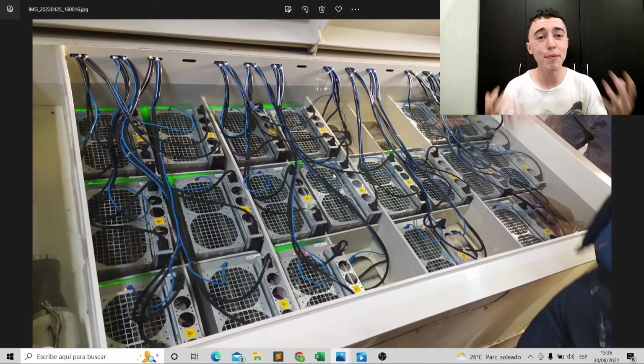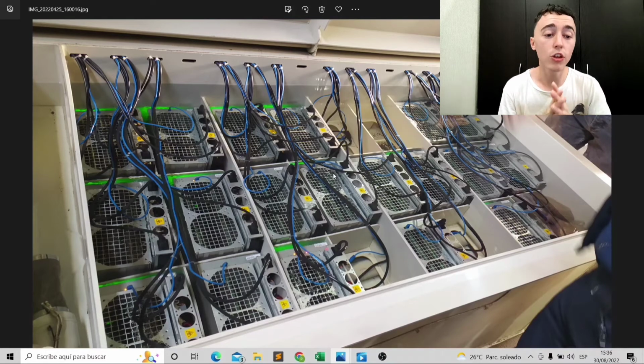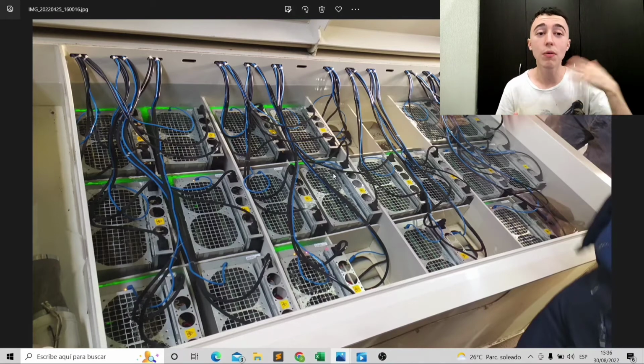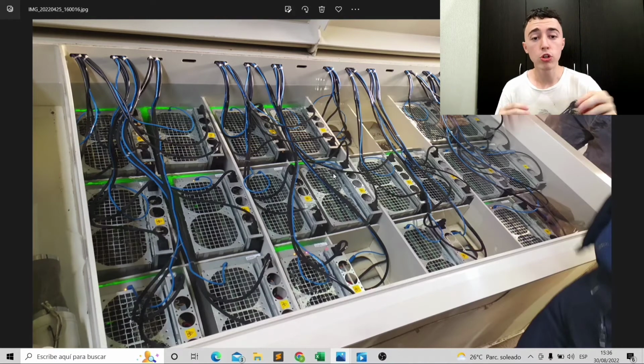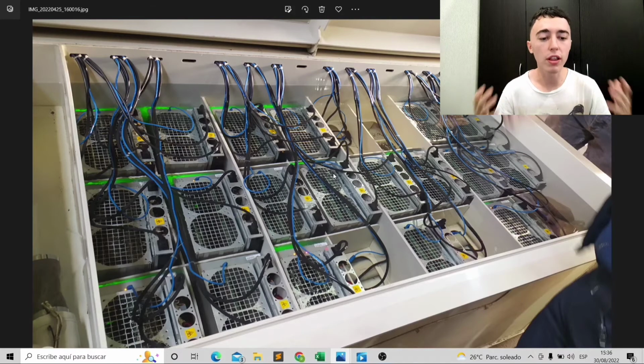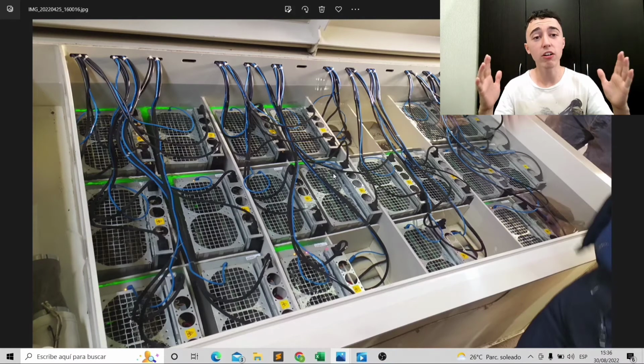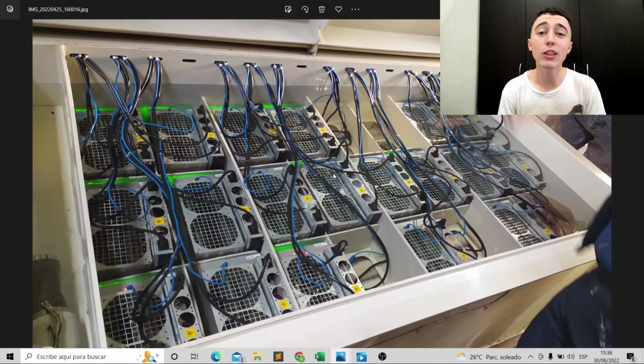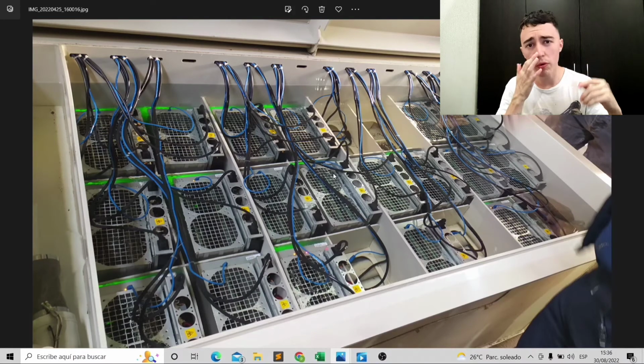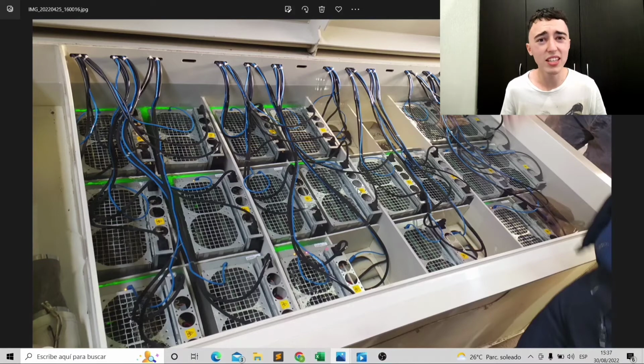So the problem is it's very expensive, but there's a benefit: you can overclock your ASIC to get more hash rate. How does overclocking work? It's the same as in a mining rig for GPUs, you overclock your GPUs and get better results. In ASICs you can't do that directly with air ventilation, because they get too hot, the chips get too hot, and it's not safe to have them that hot, over 80 degrees is not good. But with immersion cooling, they stay pretty cold, around 60 degrees, which is fine, perfect. I'm talking in Celsius.